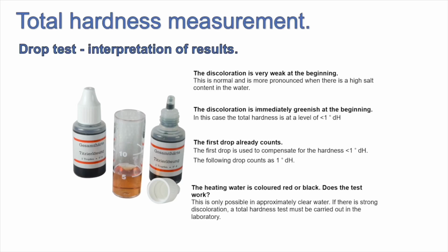The heating water is coloured red or black. Does the test work? This is only possible in approximately clear water. If there is strong discoloration, a total hardness test must be carried out by a laboratory.